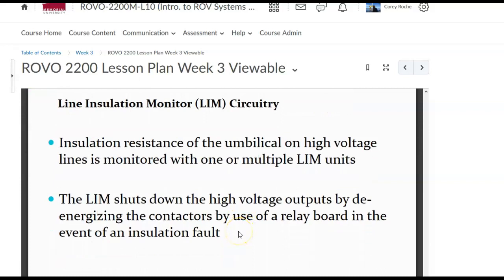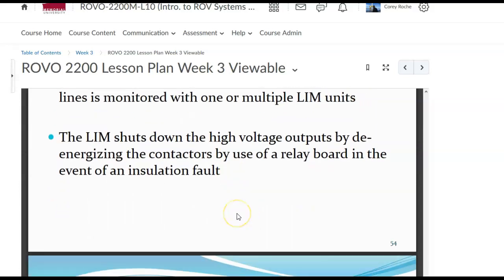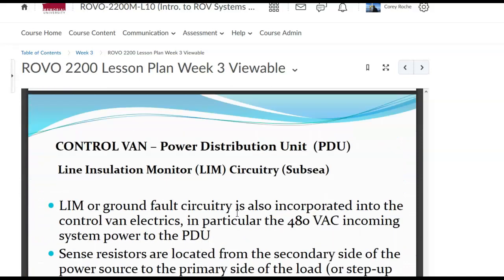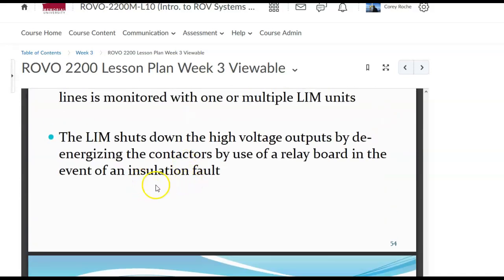Line insulation monitor, LIM circuitry again. Insulation resistance of the umbilical and high voltage lines is monitored with one or more LIMs. So insulation being the covering of the wire, right? If that breaks down, you'll have a ground fault, a leak. The LIM shuts down high voltage outputs by de-energizing the contactors by use of a relay board in the event of an insulation fault. So an insulation fault could be like bend radius. You'll hear me say that in 2 or 4 years constantly, depending if you're doing the 2-year course or 4-year course.